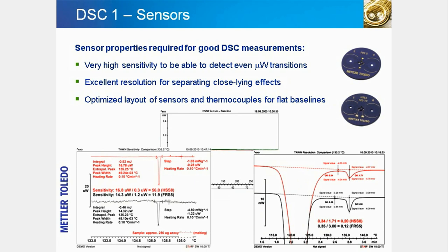The sensors in the Mettler Toledo DSC-1 are the most important components of the instrument — they determine the quality of the measurement. Two different sensors are available for the DSC-1. The most frequently used is the full-range, or FR-S5, sensor. The high-sensitivity, or HSS-8, sensor is recommended for samples that produce only a very low signal intensity. The bottom part of the slide displays results comparing the sensitivity and resolution of both sensors. Better sensitivity means it is possible to detect smaller thermal effects, or to use smaller sample amounts. The measurements were performed according to the TAWN test guidelines, a universally recognized procedure used to test the performance of DSC instruments.